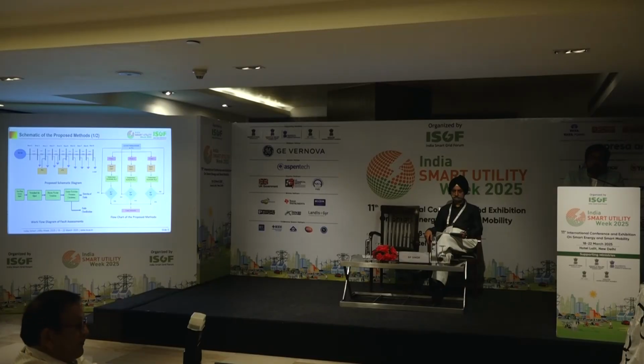Since the magnitude of the fault current is very minimal, it is very difficult to understand the fault. So we apply kurtosis analysis and DWT analysis to get the kurtosis data, and create a thumb rule comparing the data with respect to normal healthy condition. If the value of kurtosis is more than the reference value within some range, we consider it a fault.